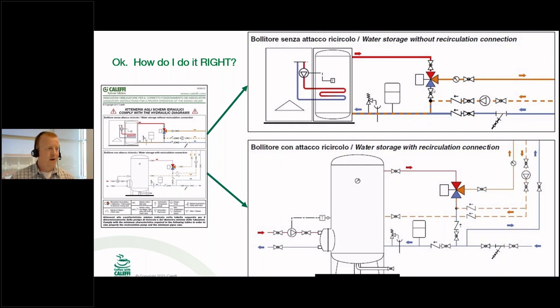That's the whole premise behind domestic hot water recirc, is that you're maintaining a temperature to eliminate wastewater and things like that, and so people can get hot water quickly. But you'll notice that there's this other drawing here down at the bottom, very similar to the drawing that we talked about with the two globe valves, but you'll notice that the globe valves in this scenario, they're not there. Okay. They are not there. You'll see that recirc is going to come back, it's going to split, and you're going to have check valves, which are great as long as they're in the right spot. And you're going to have a tie-in here at the cold inlet of the mixing valve.